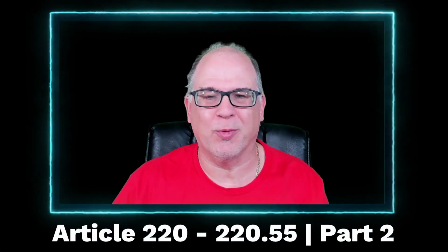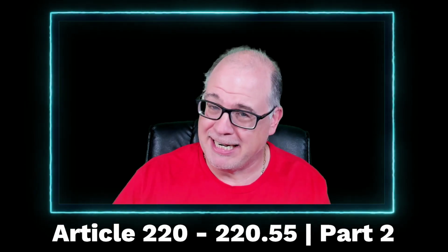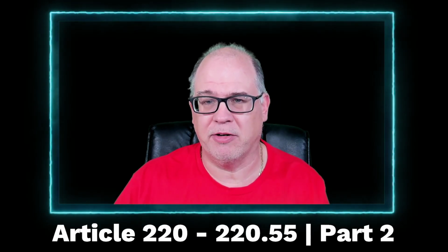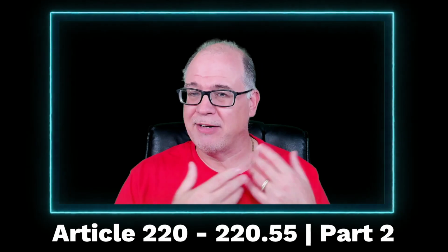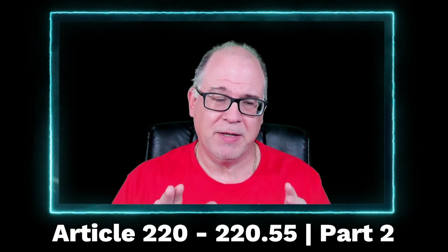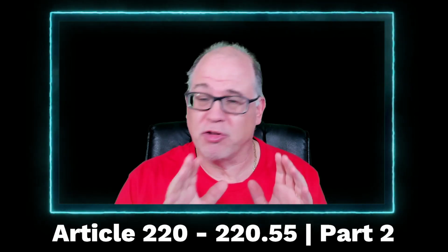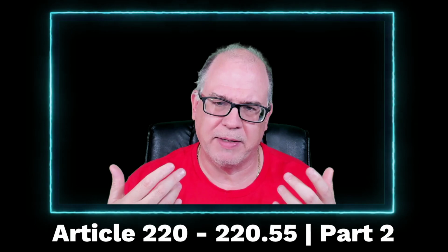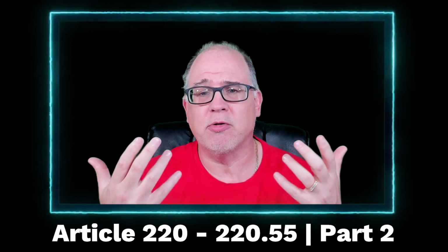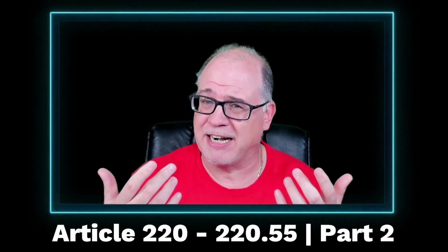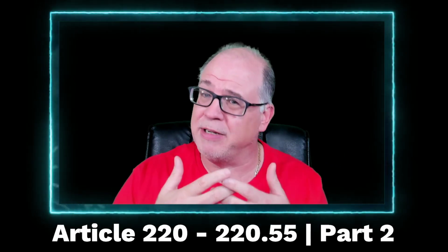In this episode, we're continuing our journey into range calculations, cooktop calculations, and in-wall mounted oven calculations. If you haven't watched part one of this series, it's really important that you go do that, because we cover the branch circuits when you use the nameplate, and what happens when you have a cooktop and a wall-mounted oven and you combine them to treat them as a single range. I know it's not a range, but you treat it as a range.